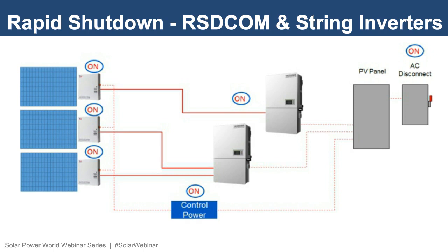With our array defined, let's discuss how this equipment works together to achieve code compliance. As I explained previously, the rapid shutdown combiners require an external control power circuit to function. Most often, the PV panel board is the most logical source for this circuit. Whether it's a 208-120 or a 480-277 service, an extra circuit from this panel can be allocated to supply control power to the combiners.